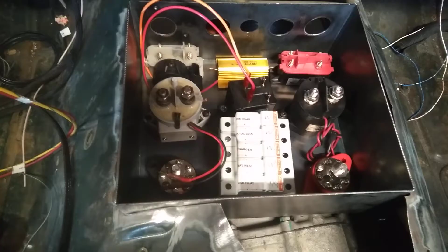Back up a little bit. On the right side of the box is where all the positive comes in. The far right hole in the back is where the positive for the battery comes in, and the one next to that is the most positive terminal from the battery that'll go straight onto that contactor. On the far left side, we've got two mirrored terminals: the one on the far left is for the battery inverter negative, the drive unit negative, and the one just next to it is for the battery most negative. Both of those will go to the contactor on the left.